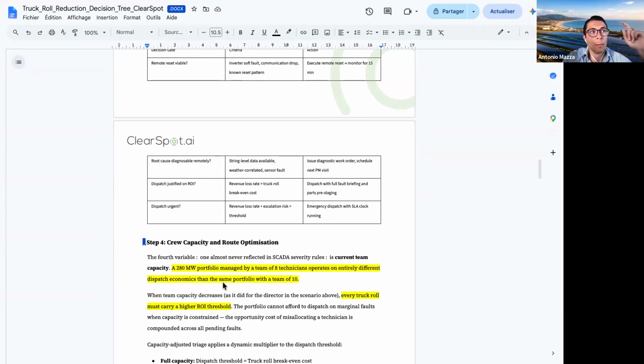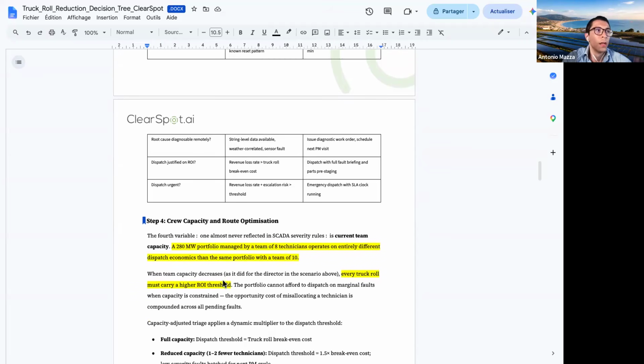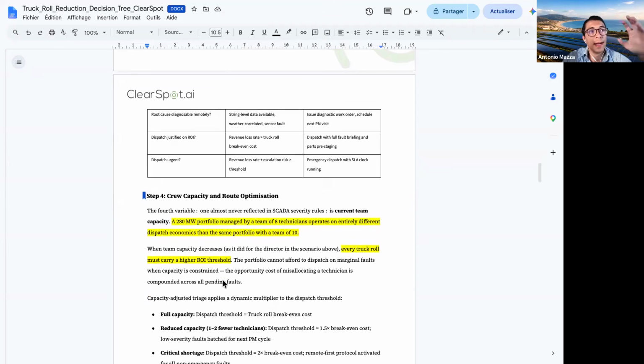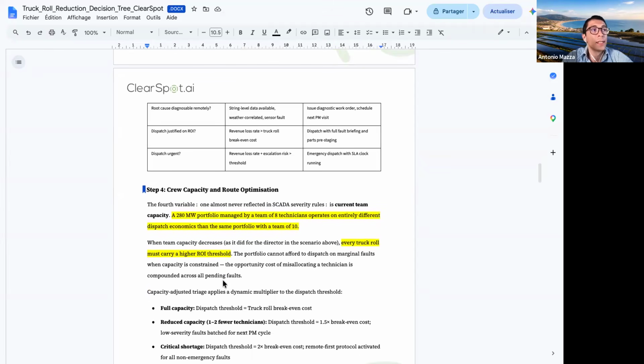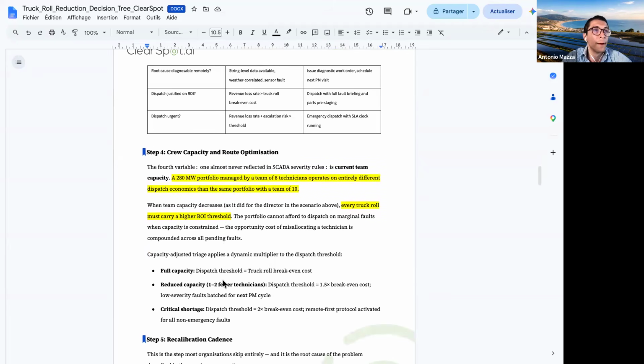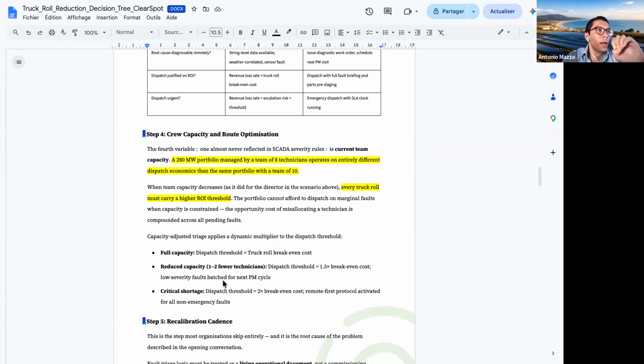One factor almost never reflected in SCADA severity rules is the current team capacity. A 280 MW portfolio managed by one technician operates on entirely different dispatch economics than the same portfolio with a team of 10. So every truck roll, and we do this autonomously in our platform, for instance, must carry a higher ROI threshold. Capacity adjusted triage normally applies some dynamic multiplier to the dispatch threshold.